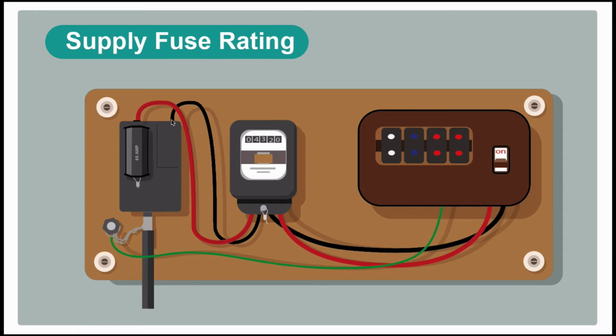Because of the tails, if you need to increase the supply, they'll check that everything on their end is able to do that. They won't just come around and stick another fuse in, a 100 amp fuse. They'll check what's going on with their setup, see if it's suitable for a larger supply. And also the tails will need to be upgraded as well. So that would be the metering people that would need to be doing that. So yeah, if the supply fuse needs to be increased, if you need a larger rated fuse for your installation, get on with the DNO straight away and get that ball rolling.